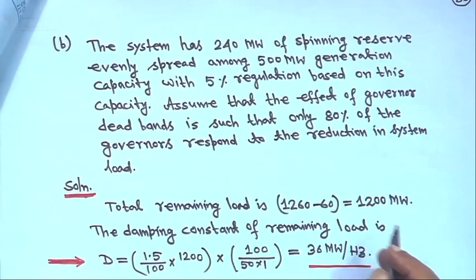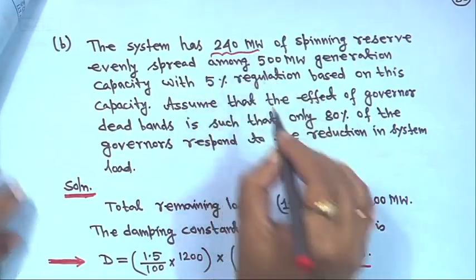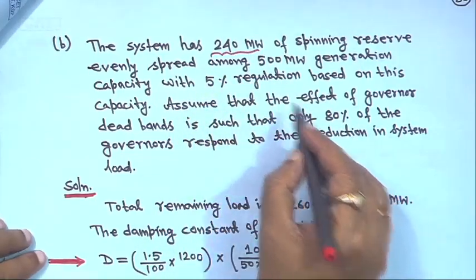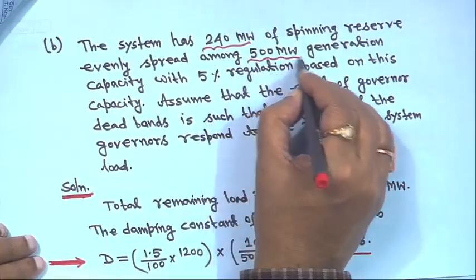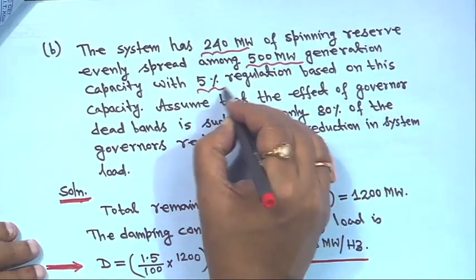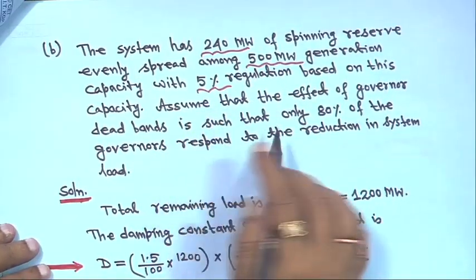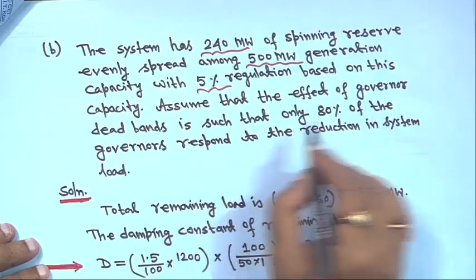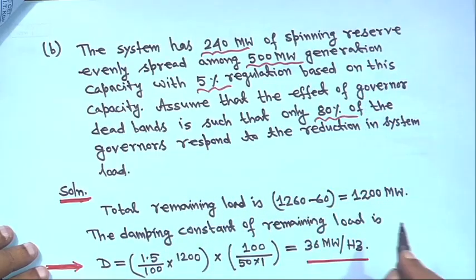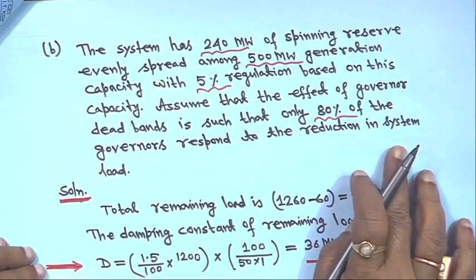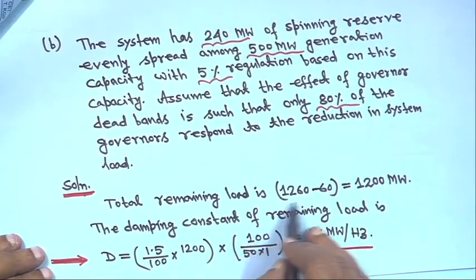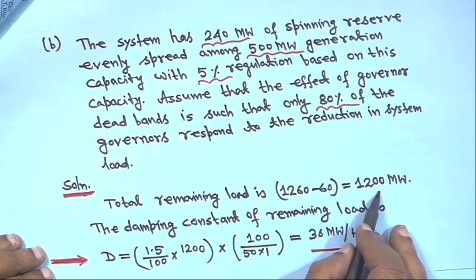Second, the system has 240 megawatt of spinning reserve, evenly spread among 500 megawatt generation capacity with 5% regulation. Assume that the effect of governor deadband is such that only 80% of the governors respond to the reduction in system load. Therefore, the total remaining load is 1260 minus 60, so 1200 megawatt.